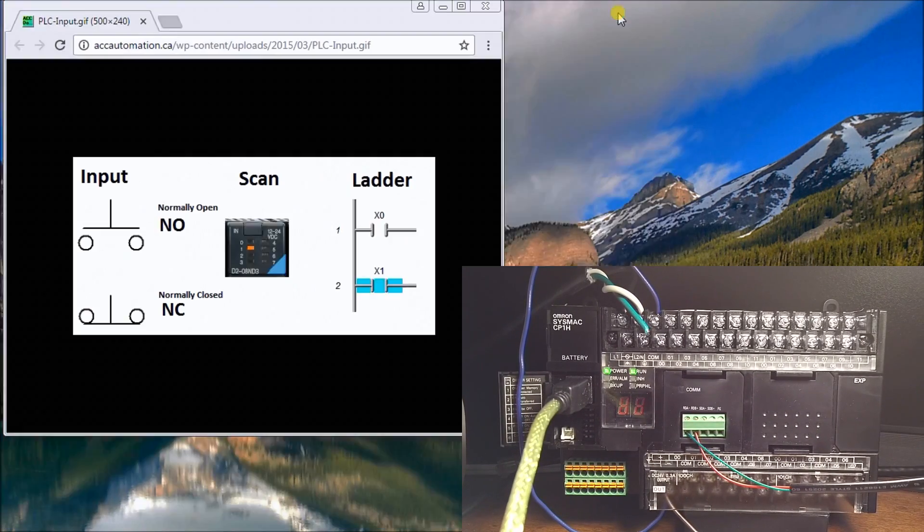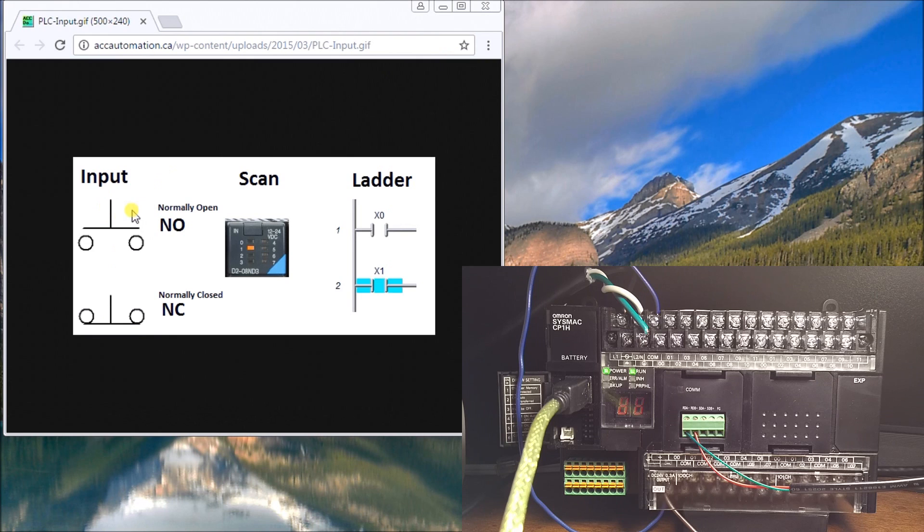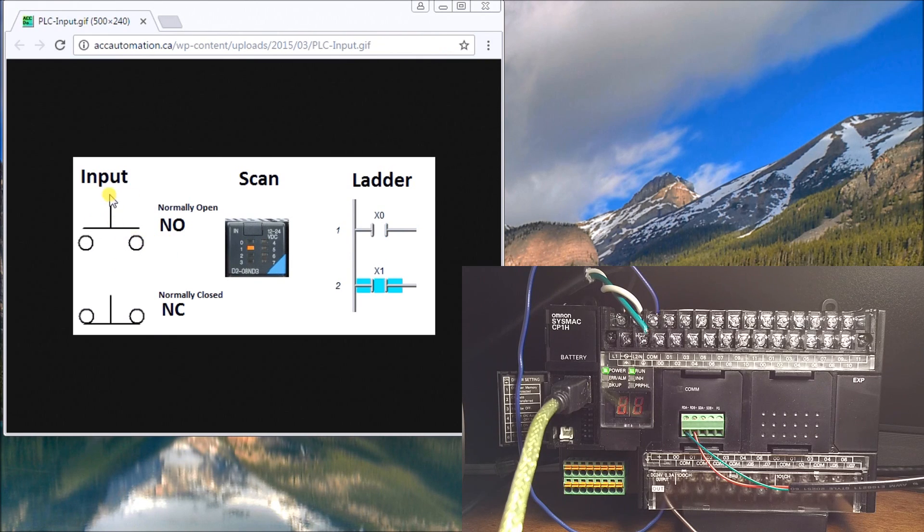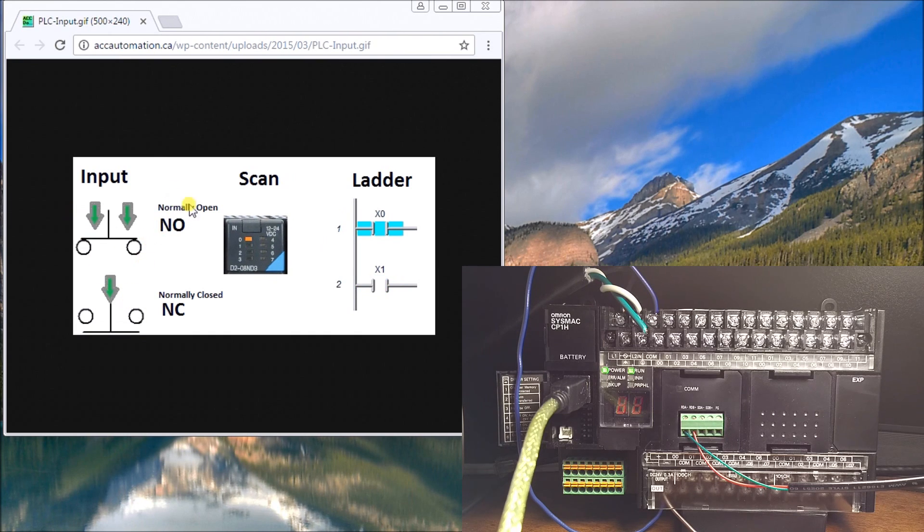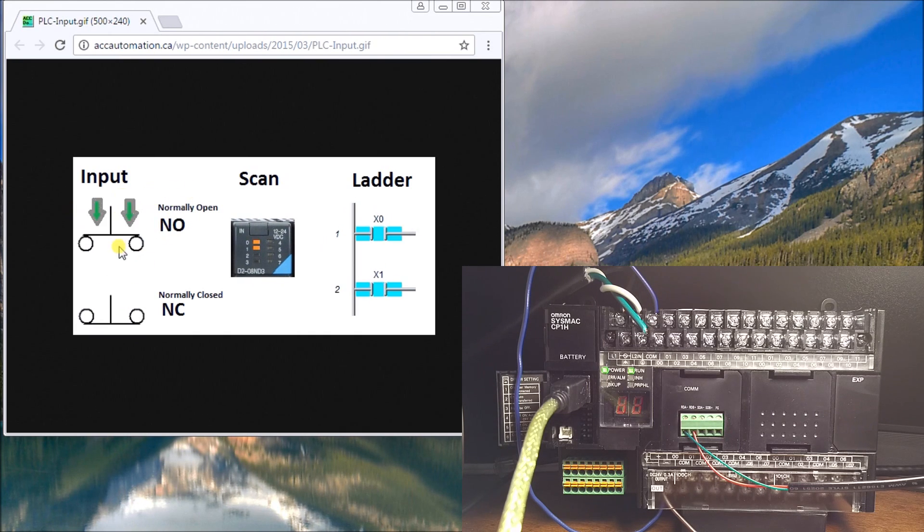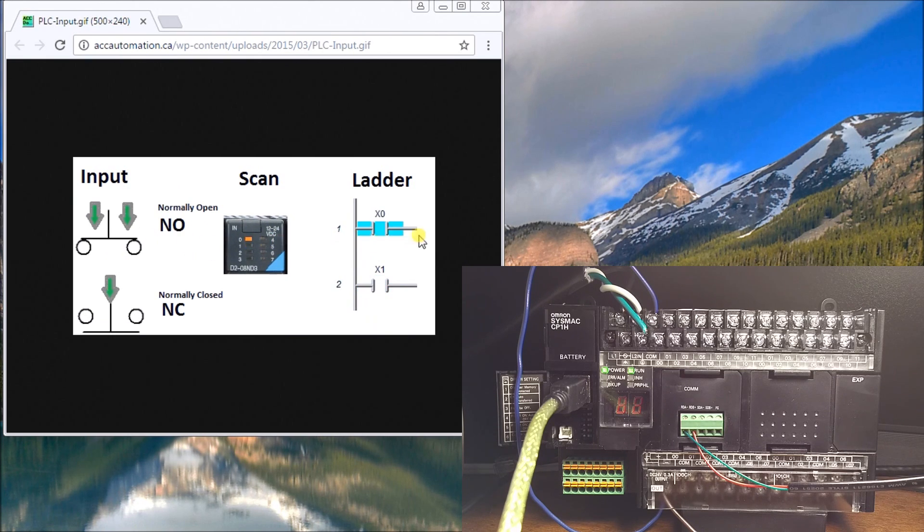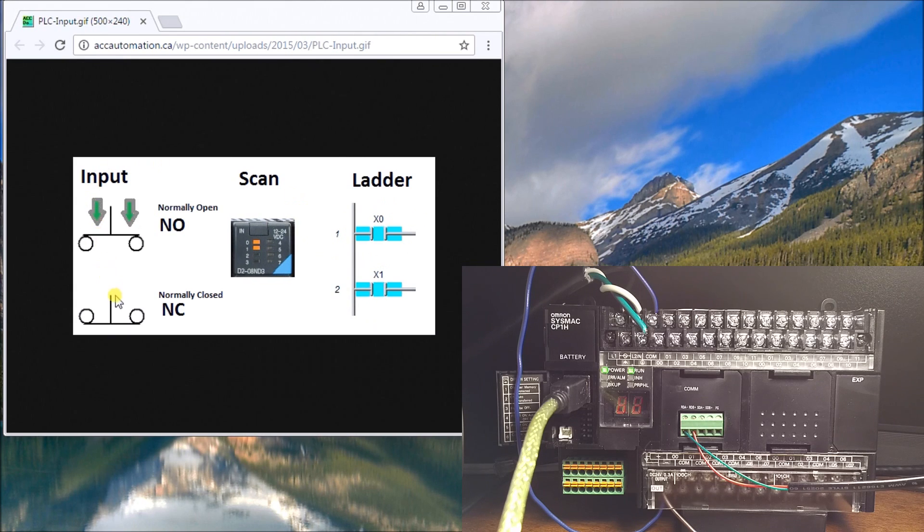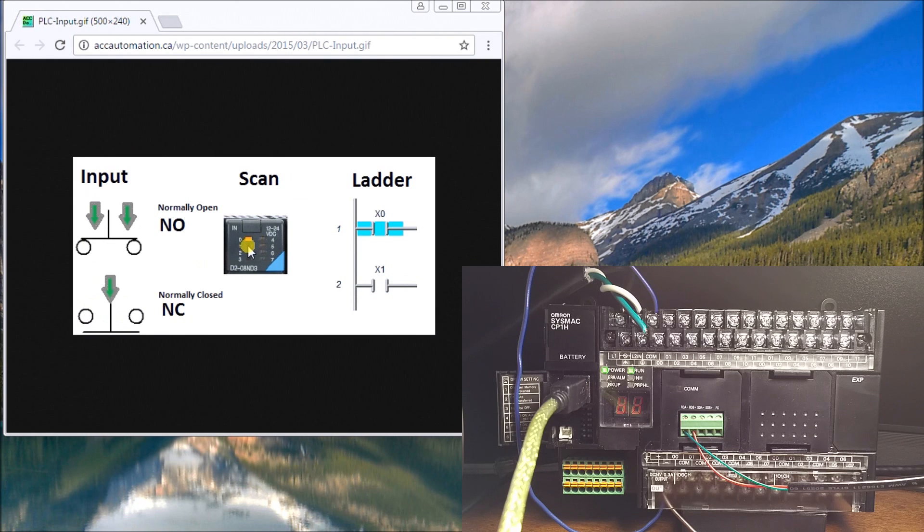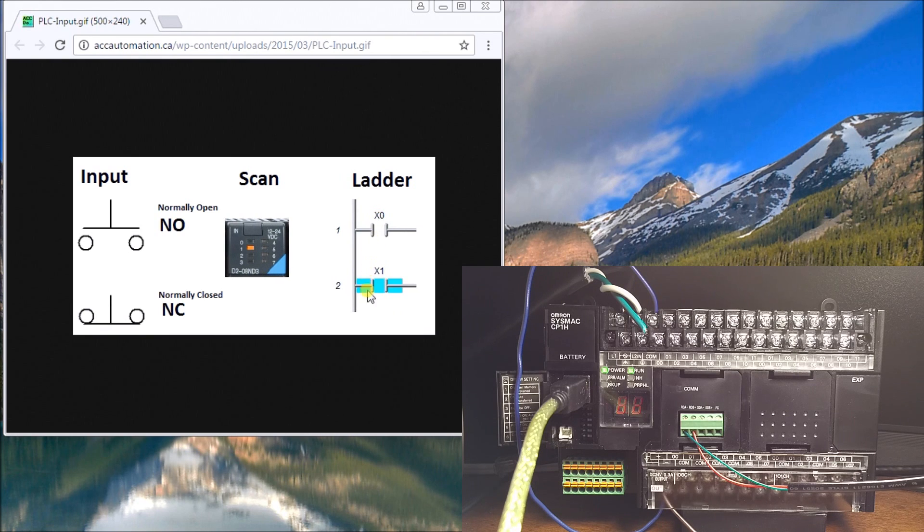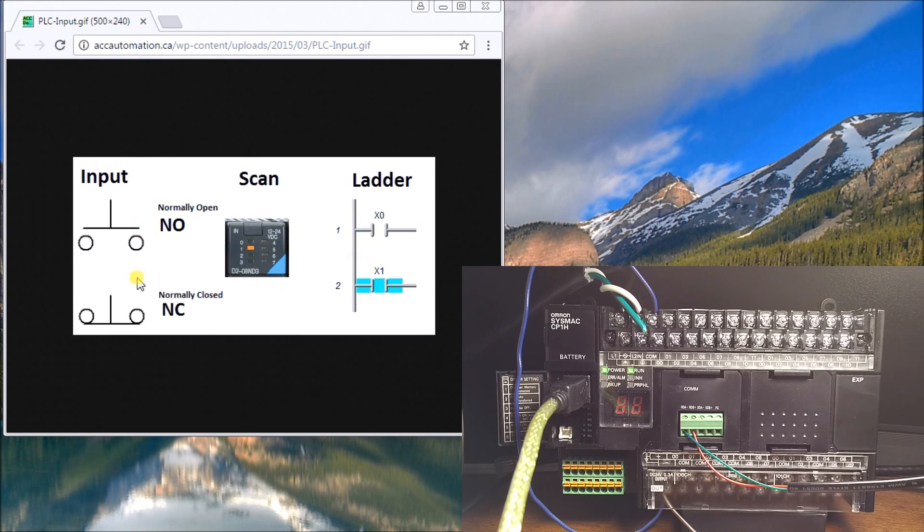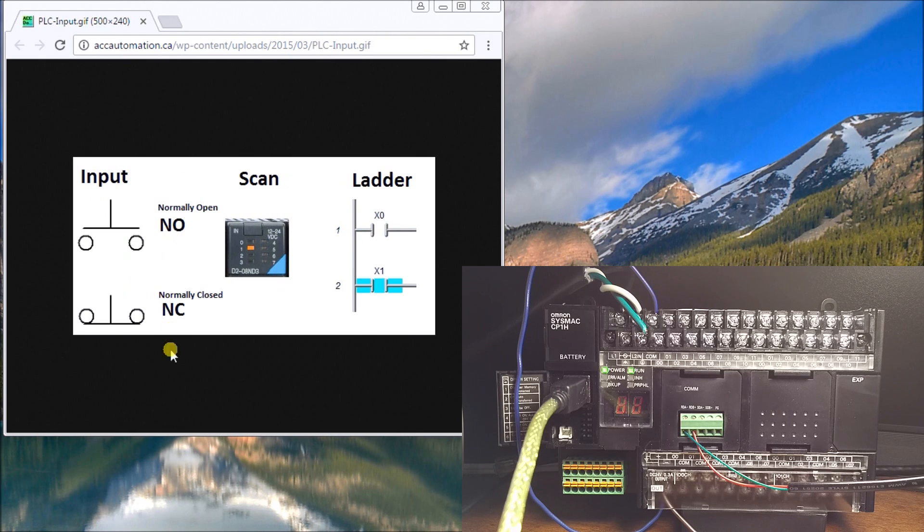If you look at the actual diagram here, you can see my input. A normally open contact means I need something to energize this, and when it does, it turns on the input. Now my normally closed actually provides an input already until someone energizes it, which then opens up the contact. So the ladder looks the same here; it really depends on how it's wired into the PLC.